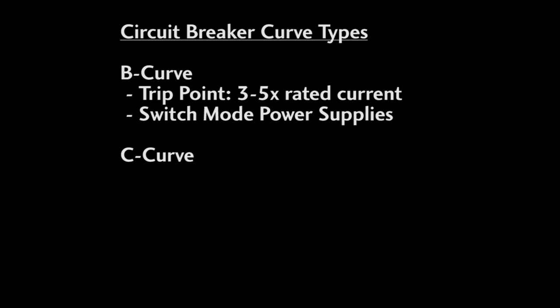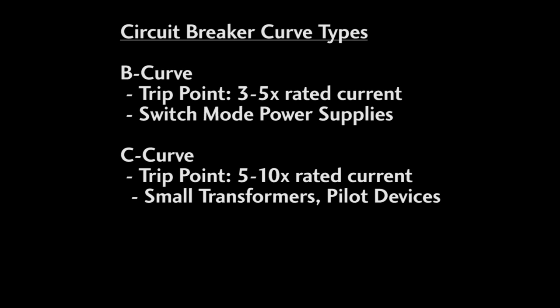The C curve has a trip point of 5 to 10 times the rated current. These are general purpose and great for small transformers and pilot devices.